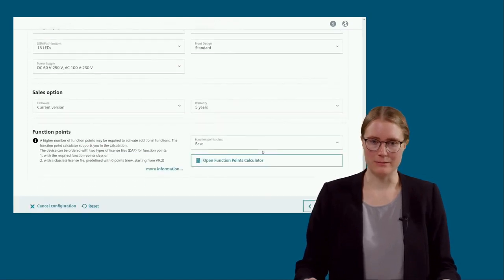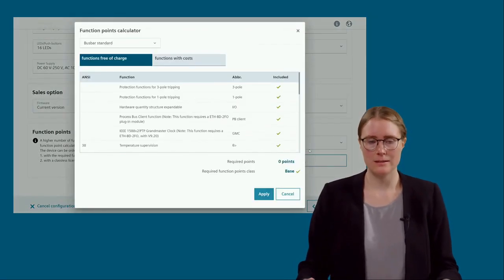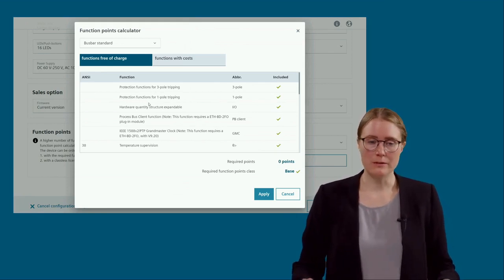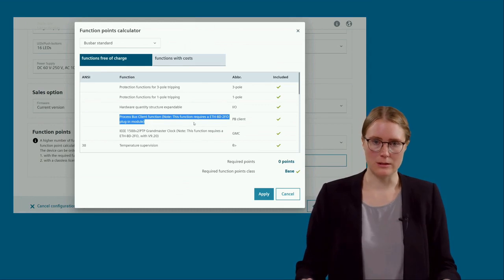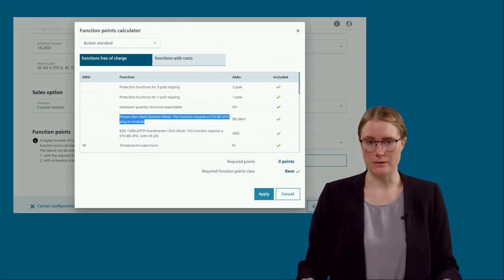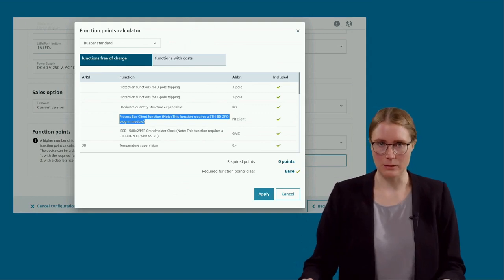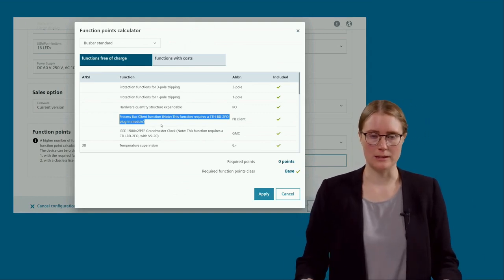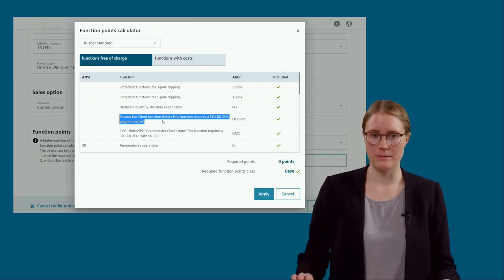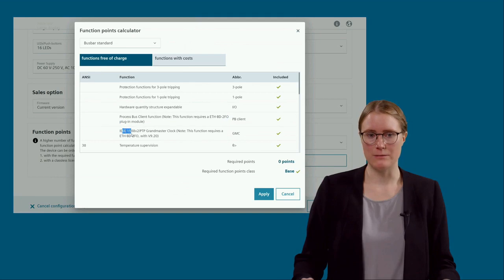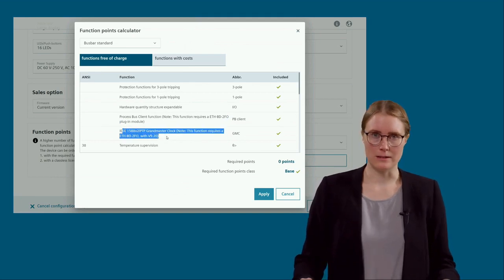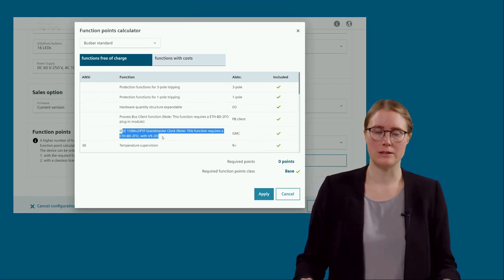And we will have another look at the function points calculator. Here, for the function free of charge, it is interesting to mention that the process bus client function is already included in the setup. So you don't need to pay function points for the communication in this case, in the 7SS85. And the IEEE 1588 PTP Grandmaster Clock functionality is also free of charge in the 7SS85. This can be used for synchronizing the sampled measured values.